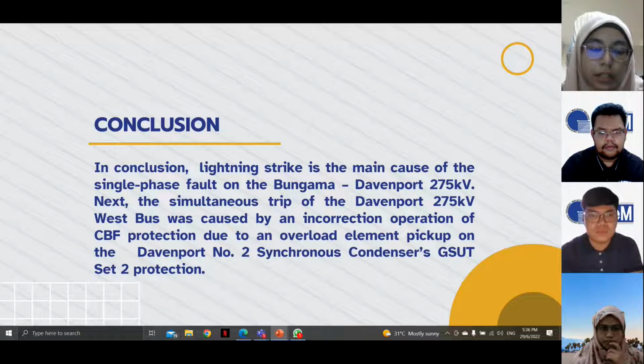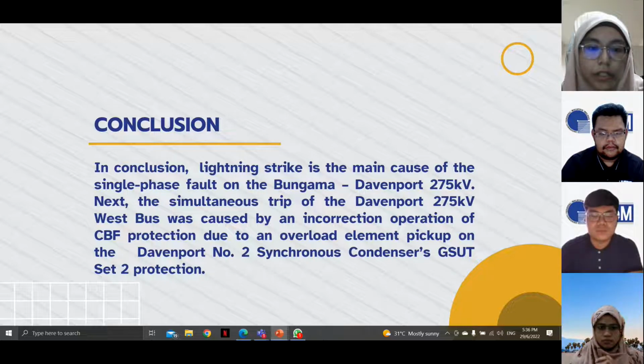Next, the simultaneous trip of the Davenport 275 kilovolt West bus was caused by the incorrect operation of the CBF protection due to an overload element pickup on the Davenport number 2 synchronous condenser GSUT set 2 protection. Thank you.